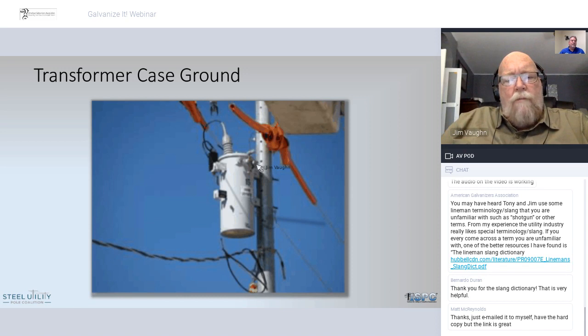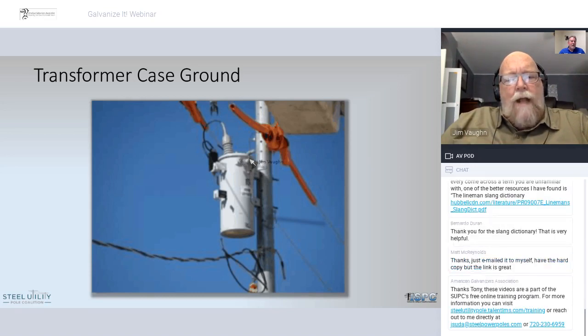The 2 outside bushings represent the 240 volts. The middle bushing is grounded. That's the neutral. So voltage between the neutral and either of the outsides is 110 volts. This neutral is connected, and you'll see the shadow of it right here, over to the steel pole.